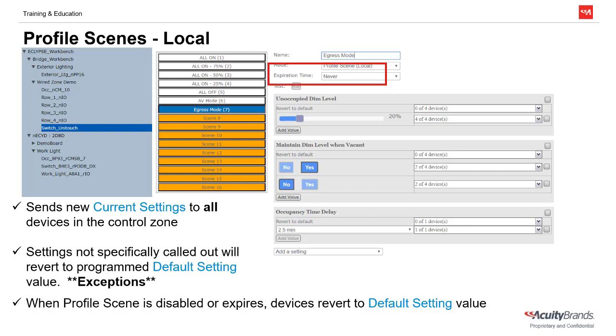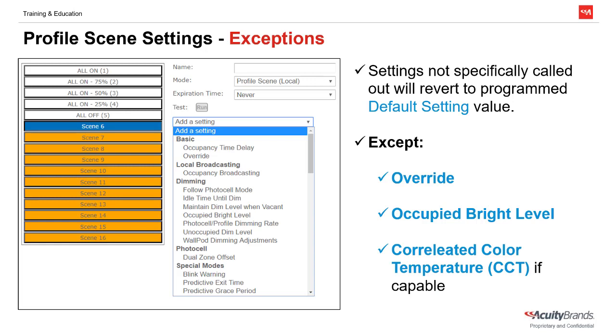Local profile scenes also give the ability to set an expiration time, adjustable from 5 minutes to 12 hours. After this time expires, devices will automatically revert to their programmed default settings. We've mentioned that settings not specifically selected from the dropdown will be told to revert to their programmed default value. This is true except for three settings that, if selected in the scene, will have immediate effects on the lights in the space. Since we likely wouldn't want the lights in a room to change dim values just because we want to change the time delay of an occupancy sensor, these three settings will remain unchanged if not specifically called out in the scene. These settings are: override, occupied bright level, and correlated color temperature, if applicable to the fixture.